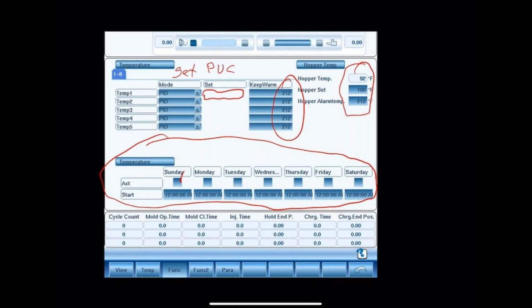It's good if you have a lot of machines and you want to spread out the demand. You can actually set these things in 15-minute increments. So all the machines will be turned on with the heats, and it'll increment every 15 minutes. It'll turn another machine on with the heats, and therefore you won't have a big power surge or demand.